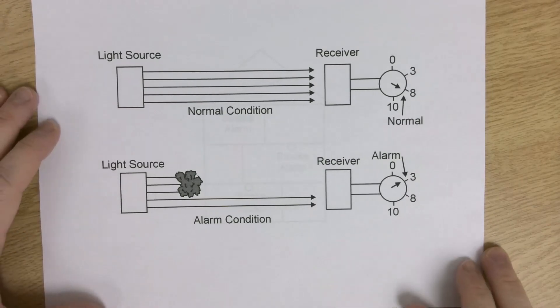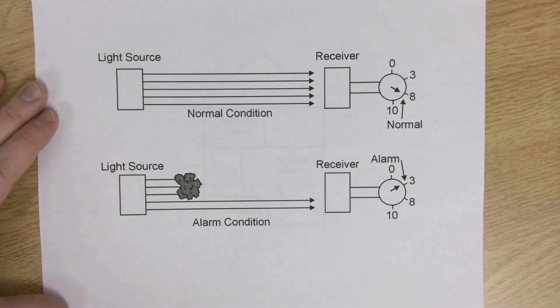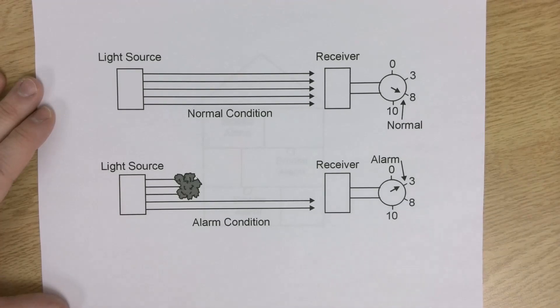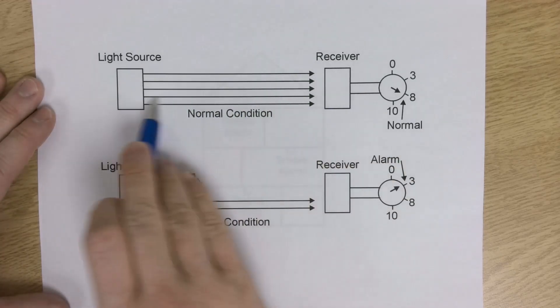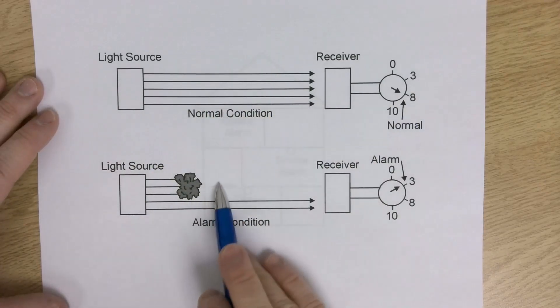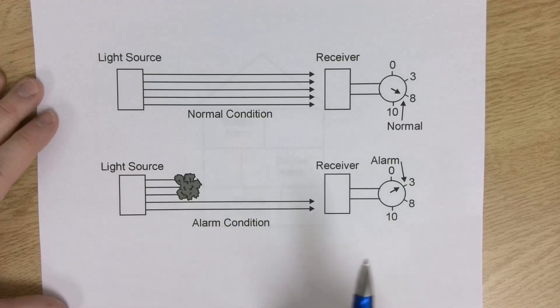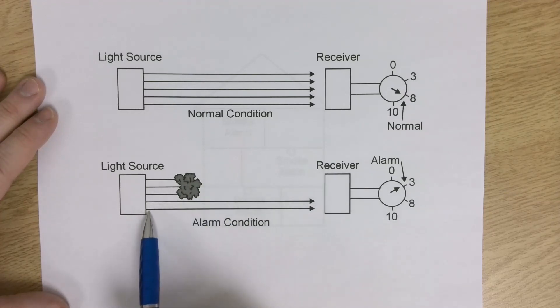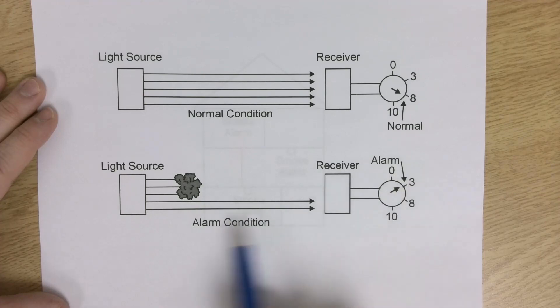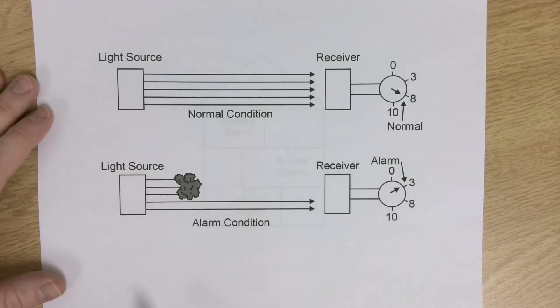The photoelectric smoke alarm uses a light source that keeps sending light to a receiver. As long as the light hits the receiver, everything is fine. But when there's a fire, or if you burn your fajita fixings and create a bunch of smoke from cooking peppers, the smoke gets in the way of the light source. The smoke alarm says it's not getting enough light to the receiver, so it starts chirping and making noise to let people know there's smoke.